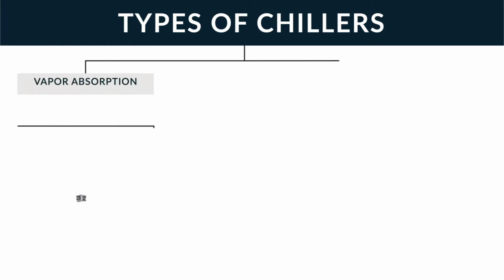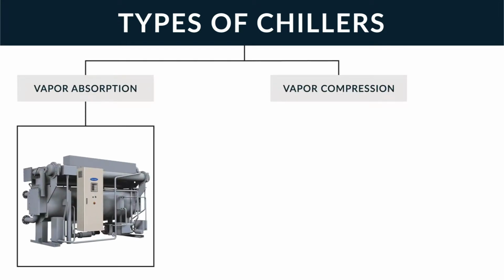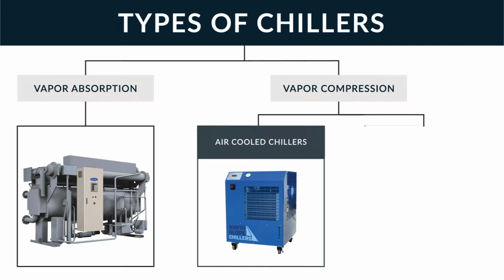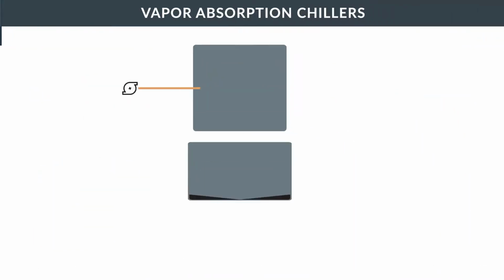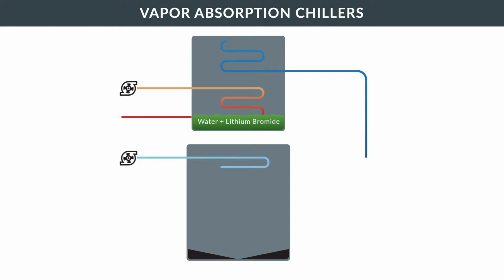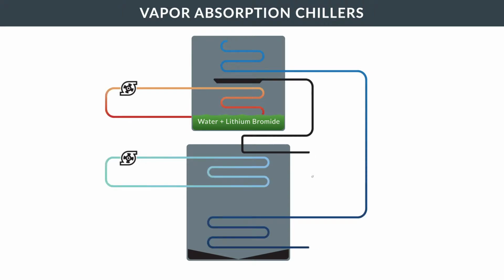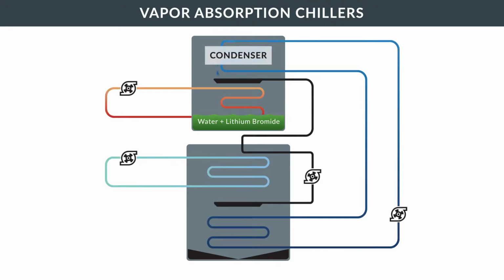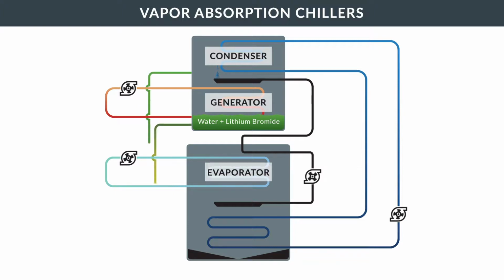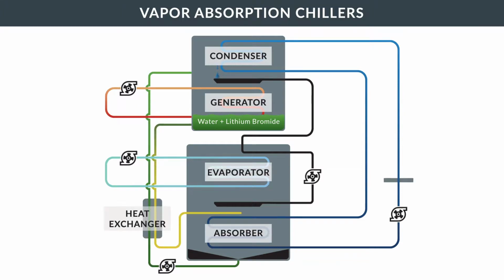There are two main categories of chillers: vapor absorption and vapor compression. Vapor compression chillers have two types: air-cooled and water-cooled. Vapor absorption chillers use heat to move the refrigerant around the system. They have 6 main components: condenser, generator, evaporator, absorber, heat exchanger, and cooling tower.